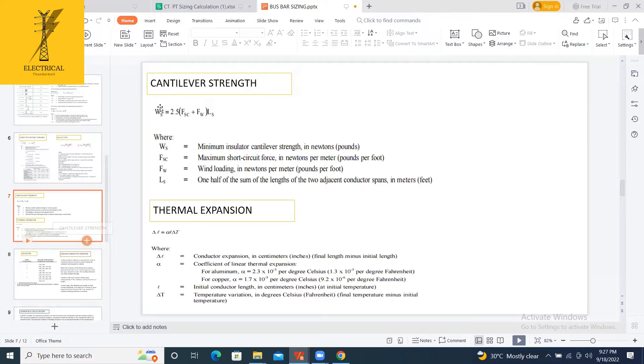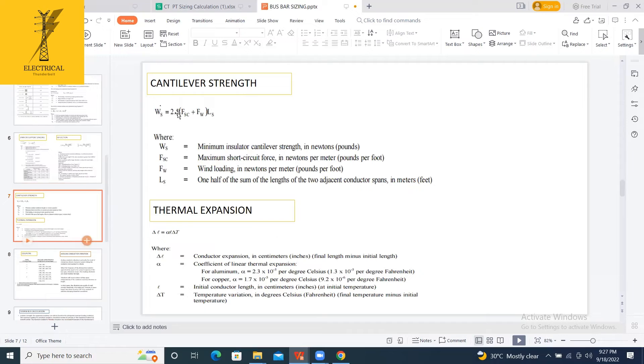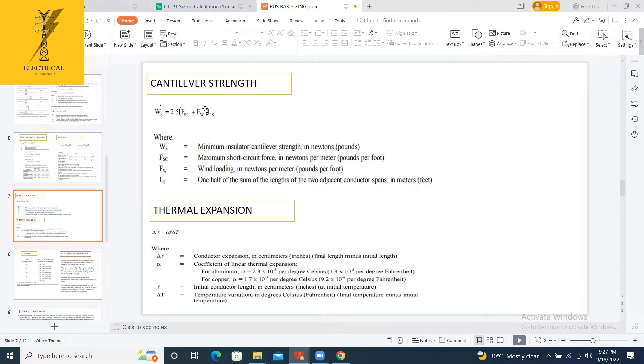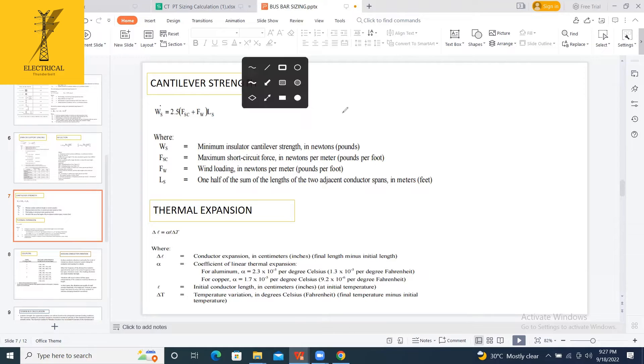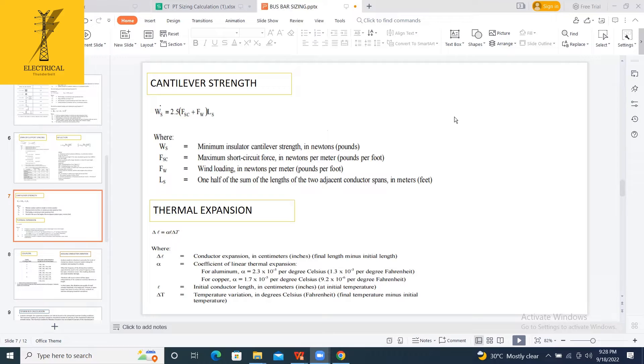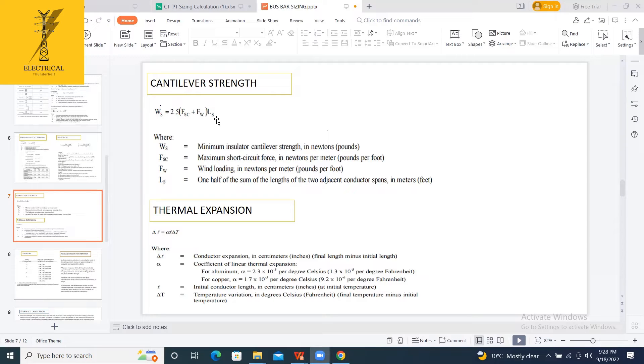The cantilever strength will be calculated. The weight, how much acting on that one, this is a formula where LS is one-half of the sum of the lengths of the two adjacent conductor spans. You can do the cantilever strength. Now, you have to select that insulator. The calculated one, suppose you got 70 kilonewtons, then you have to select the insulator that should have a cantilever strength greater than this.